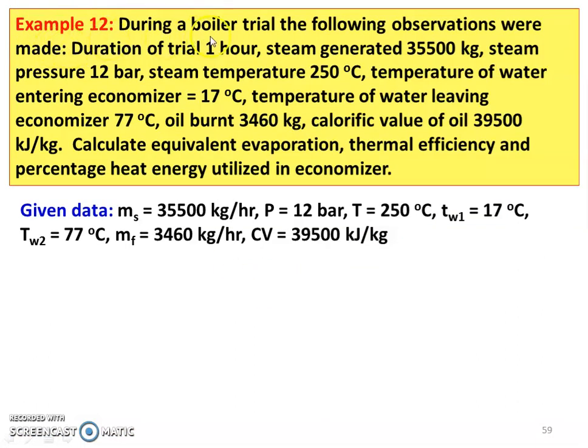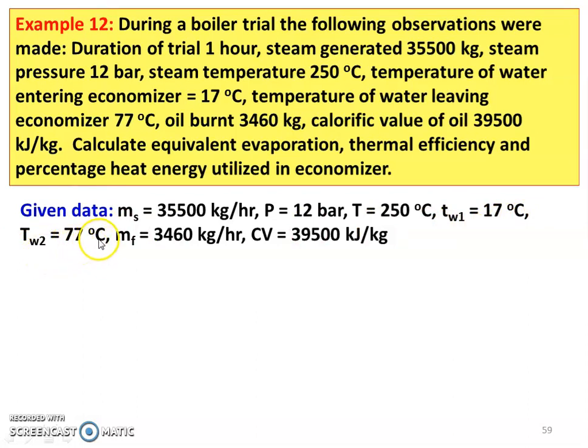The next question, example 12: during a boiler trial, the following observations were made. Duration of the trial: 1 hour. Steam generated: 35,500 kg. Steam pressure: 12 bar. Steam temperature: 250 degrees Celsius. Temperature of water entering the economizer: 17 degrees Celsius. Temperature of water leaving the economizer: 77 degrees Celsius. Oil burnt: 3,460 kg. Calorific value of the oil: 39,500 kJ per kilogram. Calculate the equivalent evaporation, thermal efficiency, and percentage of heat energy utilized in the economizer. Given: mass of steam produced 35,500 kg per hour, pressure 12 bar, temperature 250 degrees Celsius, economizer inlet water temperature 17 degrees Celsius, economizer outlet water temperature 77 degrees Celsius — with this 77 degrees Celsius water entering the boiler — mass of fuel 3,460 kg per hour, calorific value 39,500 kJ per kilogram.